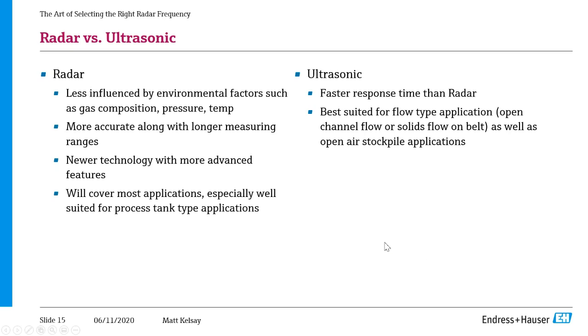Ultrasonic does have its benefits and its place for sure. For one, it's quite a bit faster response time than a radar device. So if you have something, especially in a short range, that's changing quite rapidly, an ultrasonic is a great choice for that. The other place where it really shines is in flow type applications, where we're using a level measurement to then calculate a flow. Most notably open channel flow happens a lot in the municipal market. Ultrasonics are great for that application. The other is solids flow on a belt. So if you've got any sort of solid material flowing along a conveyor belt or in a screw conveyor, auger, anything like that, an ultrasonic is better suited there as well.